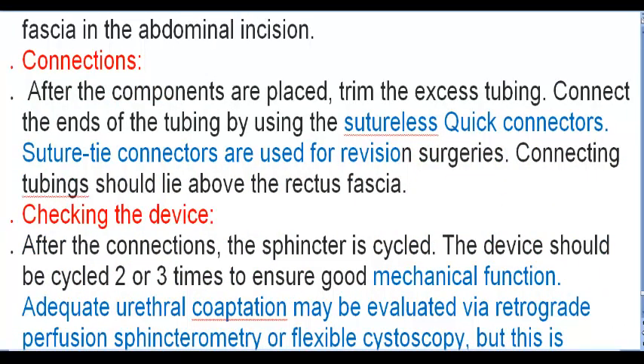Connections: after the components are placed, trim the excess tubing. Connect the ends of the tubing by using the sutureless quick connectors. Suture tie connectors are used for revision surgeries. Connecting tubings should lie above the rectus fascia. Checking the device: after the connections, the sphincter is cycled. The device should be cycled 2 or 3 times to ensure good mechanical function.